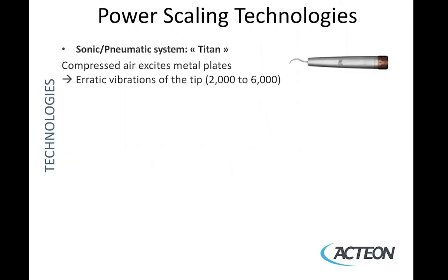There are three types of power scaling technology. The first is sonic — an example of that would be Titan. The sonic scaler uses compressed air; it's connected to the delivery system and the compressed air excites the metal stacks, creating erratic vibrations and a tip movement at 2,000 to 6,000 times per second.